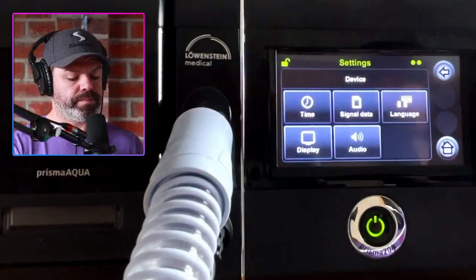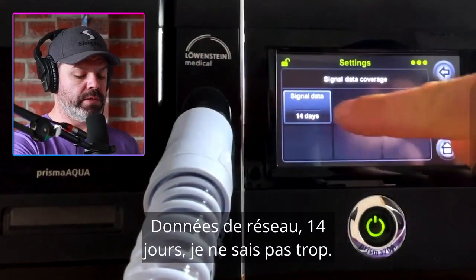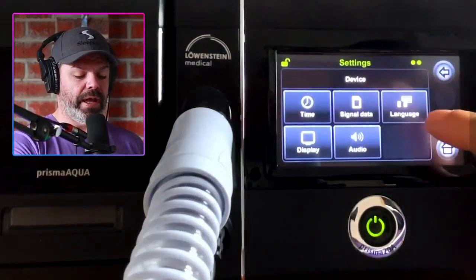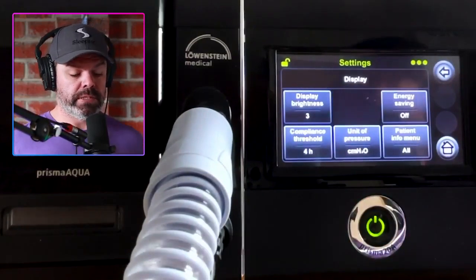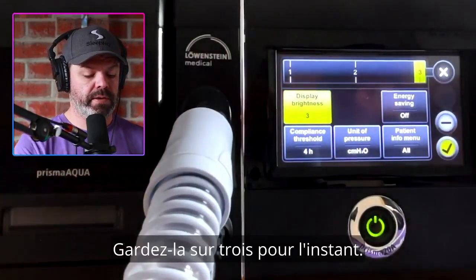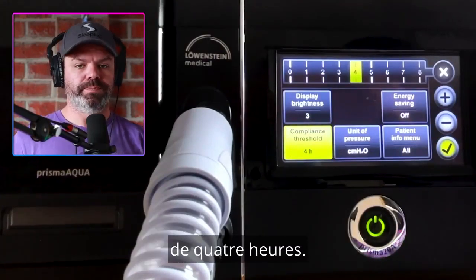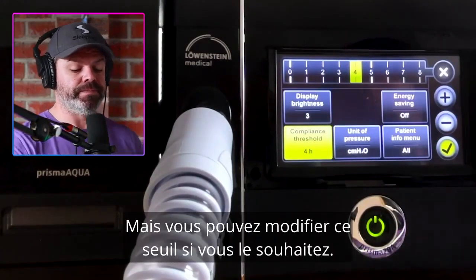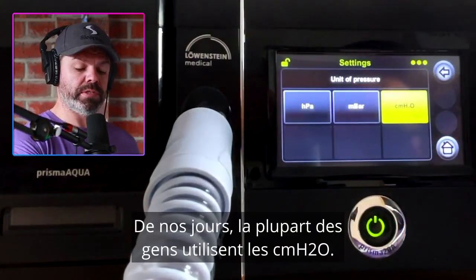Under device settings we can set our time, date, and time zone. There's also a signal data option — 14 days — I'll get back to you on that one. Under display we can change brightness between one, two, and three. We can change the compliance threshold — most companies use four hours per night to be deemed compliant, but you can change that. We can also change the unit of pressure: hPa, mbar, or cmH2O. Most people use cmH2O these days.